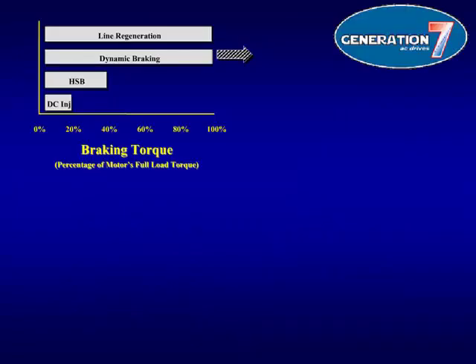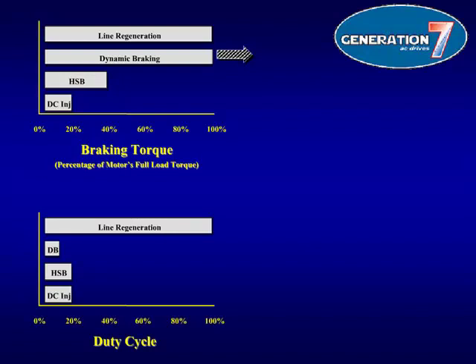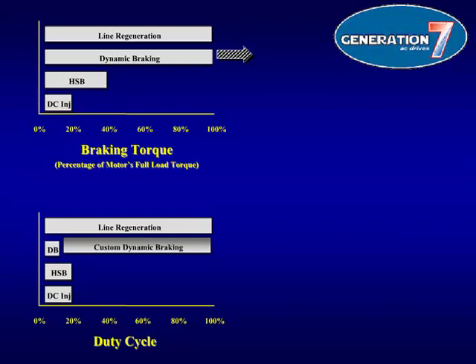Looking first at braking torque, both line regeneration and dynamic braking offer much more torque than high-slip braking or DC injection. This is important because the stronger the braking torque, the faster the stopping time. Next is the duty cycle. Because line regeneration converts regenerated power back onto the AC input lines, there is no heating of braking components to be concerned with, which is why the duty cycle for line regeneration is so much larger than the other methods. Dynamic braking offers standard packages between 3% and 10% duty cycles. Custom dynamic braking packages can increase the duty cycle, but over 50%, it is often recommended to use line regeneration instead.